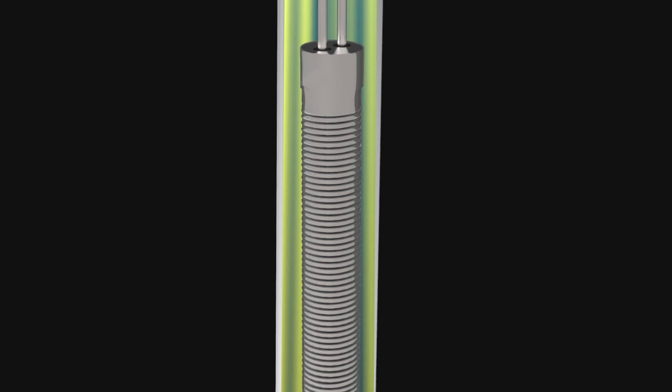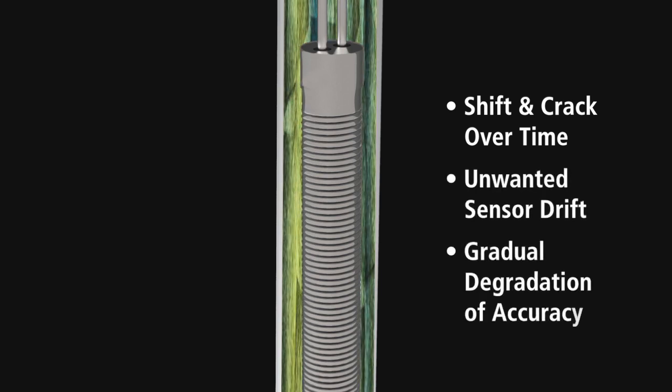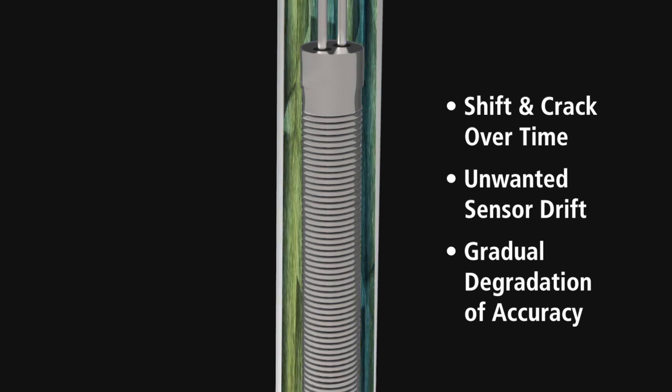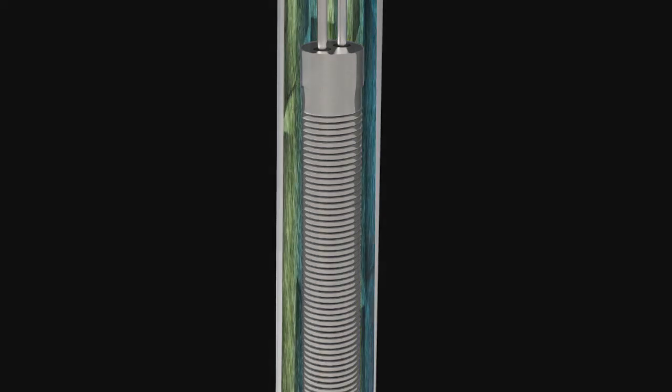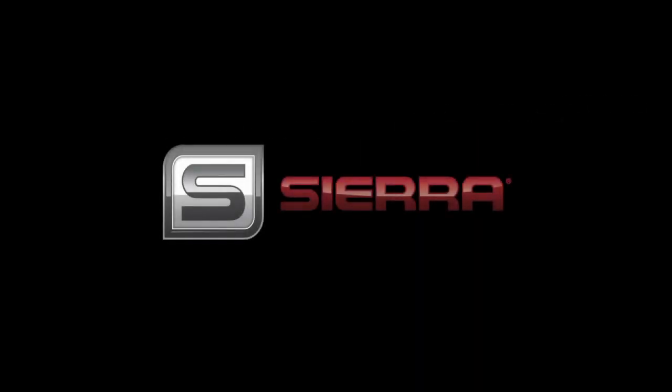Wet thermal sensor design, because of the organic potting cement used, would shift and crack over time, causing unwanted sensor drift, resulting in a gradual degradation of flow measurement accuracy. Today, wet thermal sensors are used by all industrial thermal sensor manufacturers on the market, with one exception, and that is Sierra.